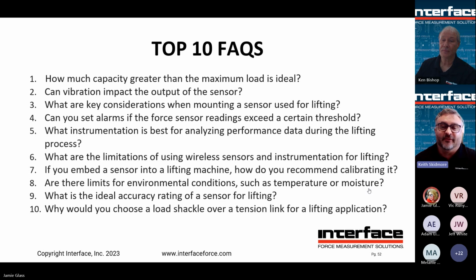So it could be that whatever the maximum possible load is, including, say, overload or something going wrong, you have to have maybe a safety factor on top of that of up to 5 times for safety purposes, for example. So it's very much application specific, and many times you might need quite a bit more safety factor or capacity in the load cell than you might expect to allow for the required safety factors.